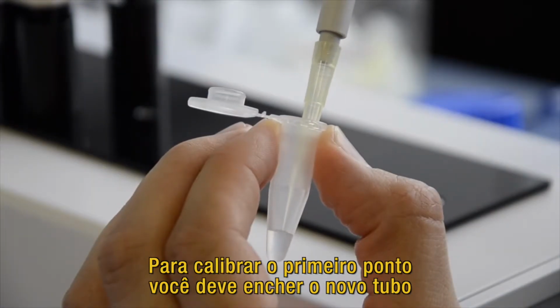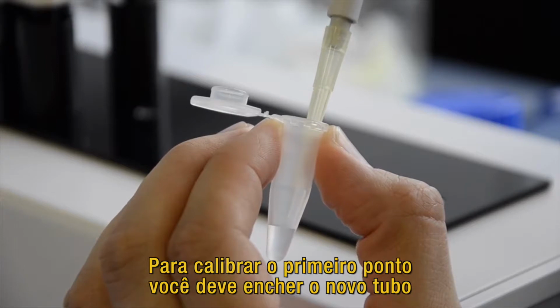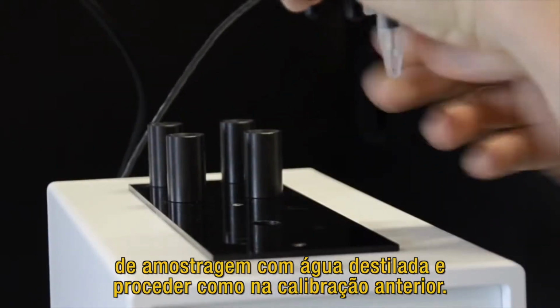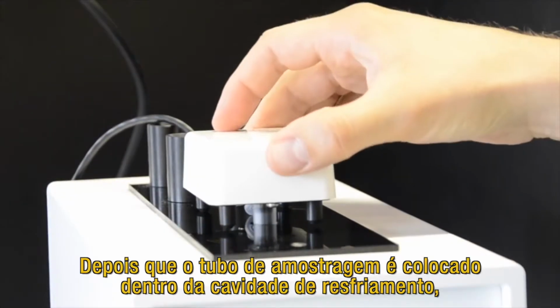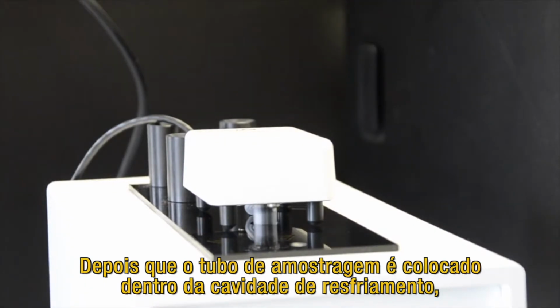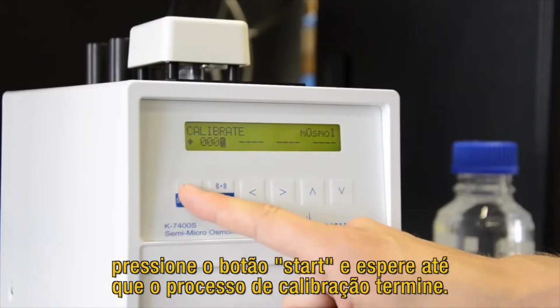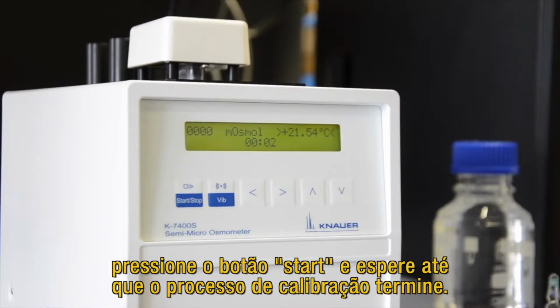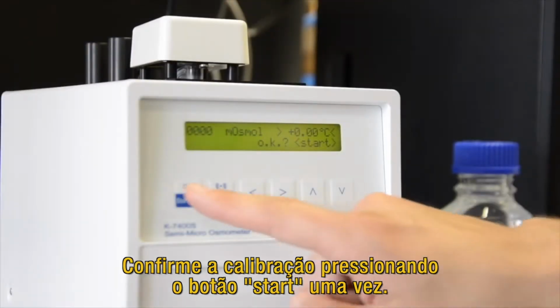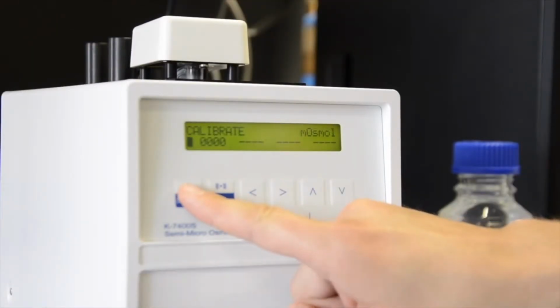To calibrate the first point, you have to fill a new sample tube with distilled water and proceed as for the previous calibration. When the sample tube is placed into the cooling cavity, press the start button and wait until the calibration process is finished. Confirm the calibration by pressing the start button once.